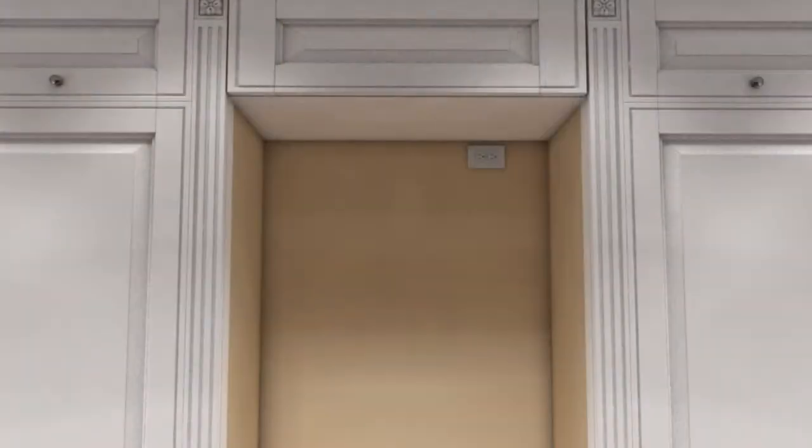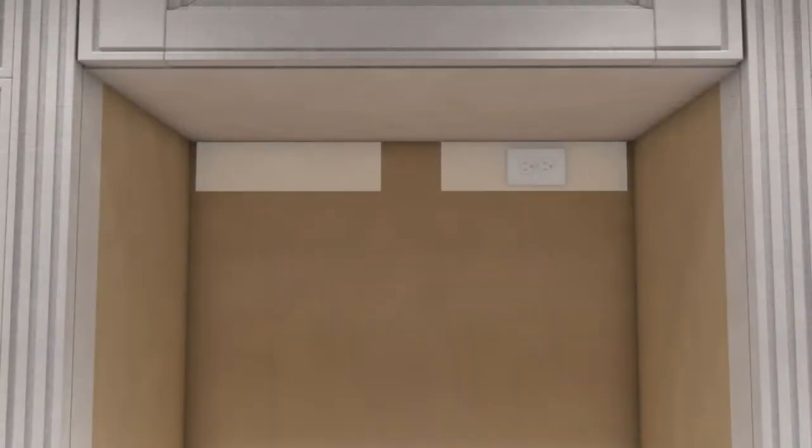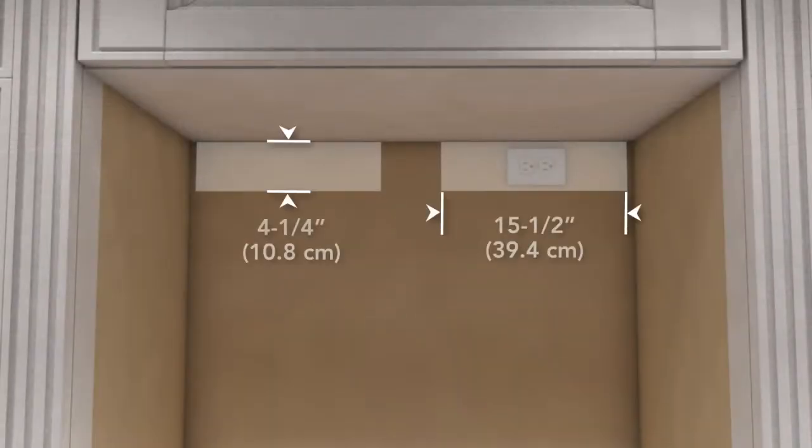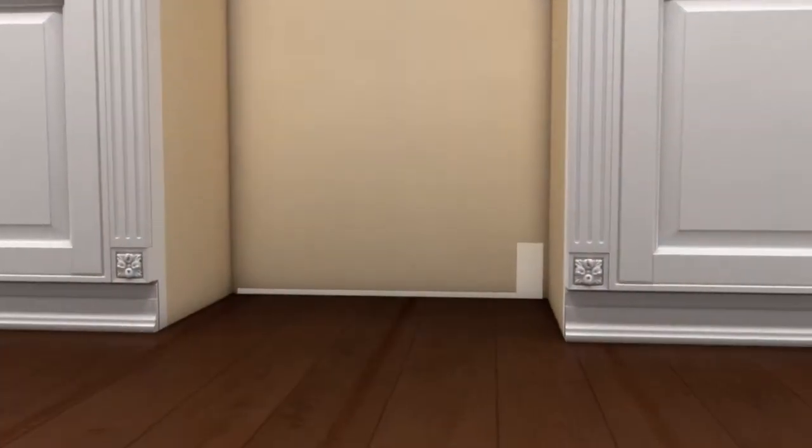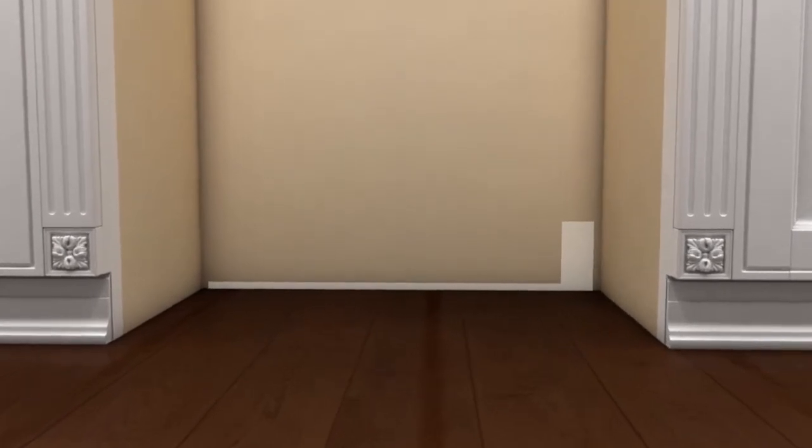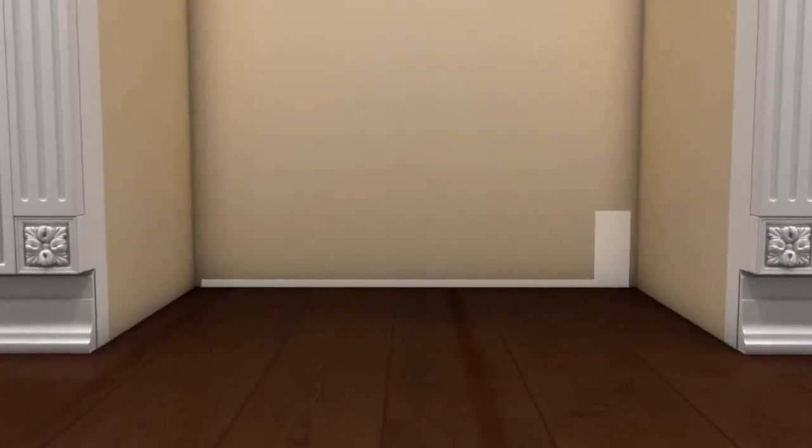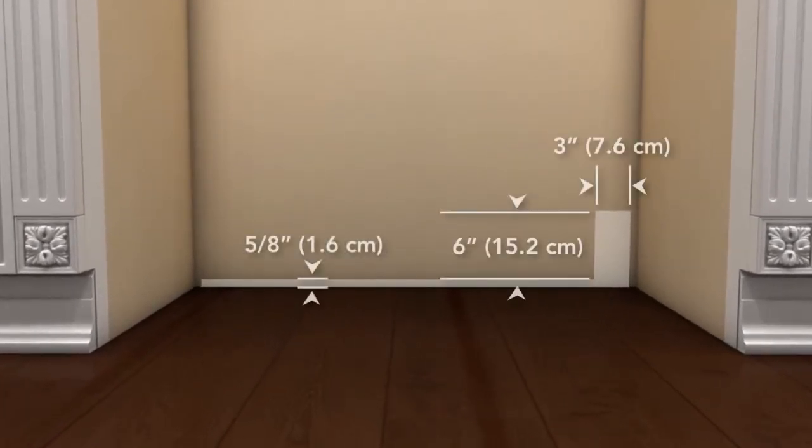The electrical outlet location can be on either side of the rear wall but must be within 4 and 1/4 inches from the top and 15 and 1/2 inches from the side. The water line entry should be located on the bottom of the rear wall within the area shown.